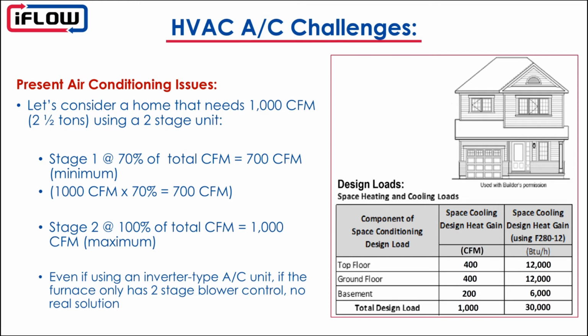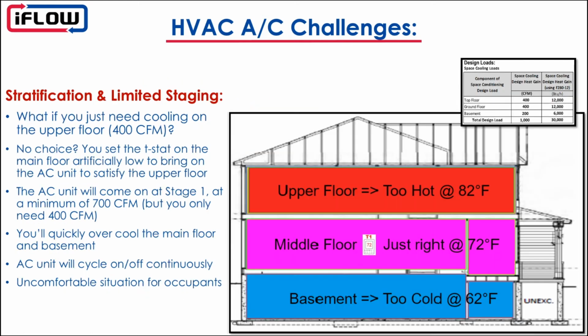Even if we use an inverter type AC, which is modulating, if the furnace blower has only two-stage control, then really it doesn't help us much in this situation. So we're still going to have this 700 and 1,000 CFM as what our blower can actually deliver. So let's see how that would work in a house.